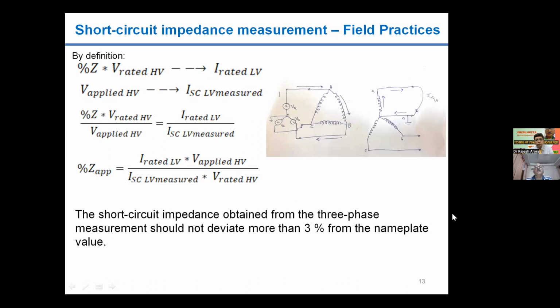So the formula is indicated and the circuit is also there. The LV is shorted, and voltage is applied on one phase of the winding. As you see, automatically to balance the ampere turns, the current will flow in the same winding of the transformer, which you are shorting on the LT side.